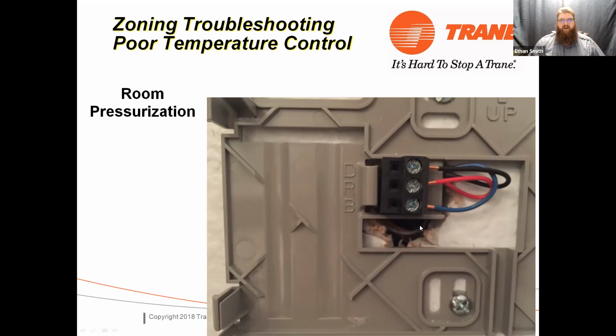Okay, so always, always, always, guys, make sure you are sealing up the holes in your walls, whether it's a zone sensor or a thermostat. Always seal up your holes. Did I mention you should seal up your holes? Okay, make sure the holes are getting sealed up. Tape is not generally a good seal unless it's backed up with some kind of putty or silicone.